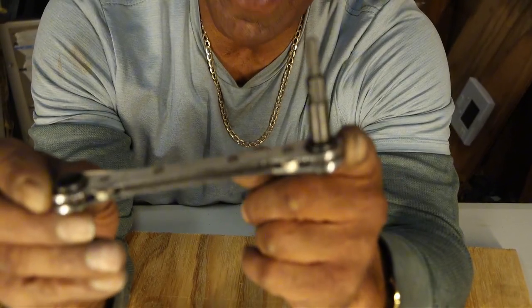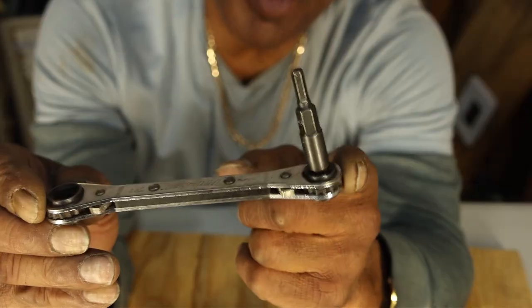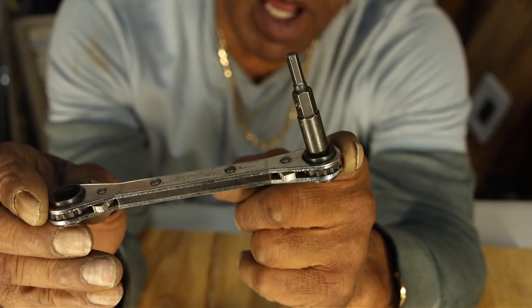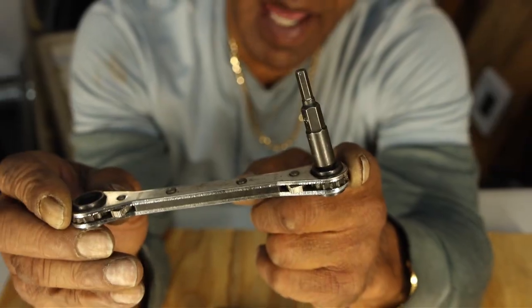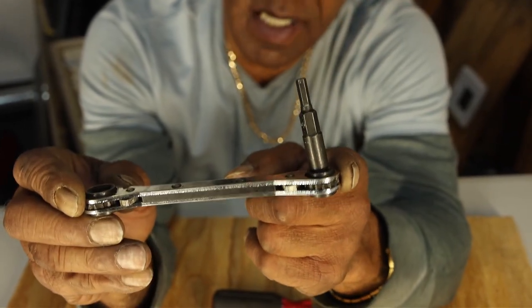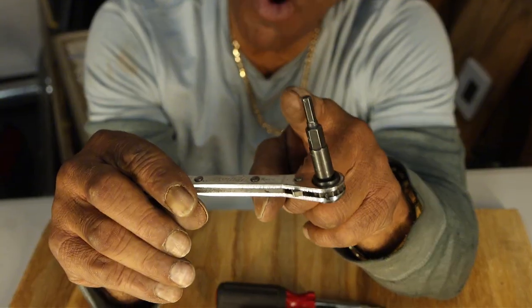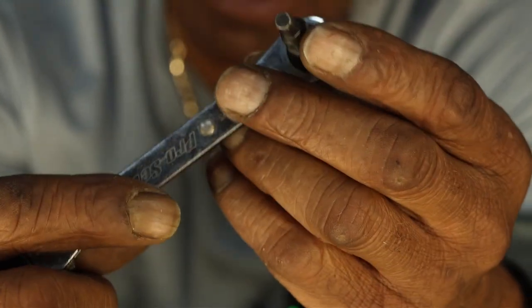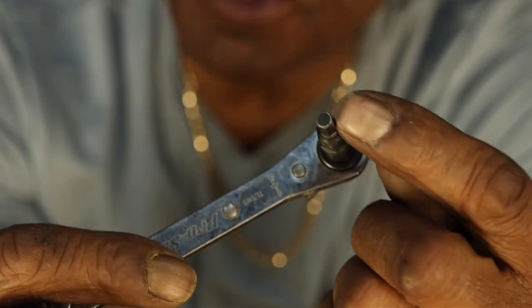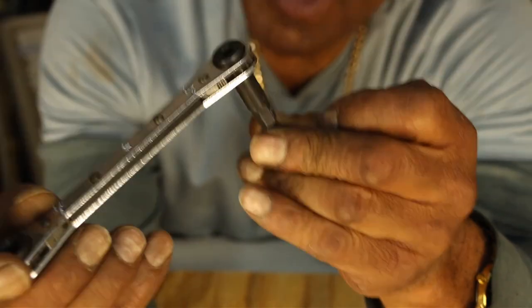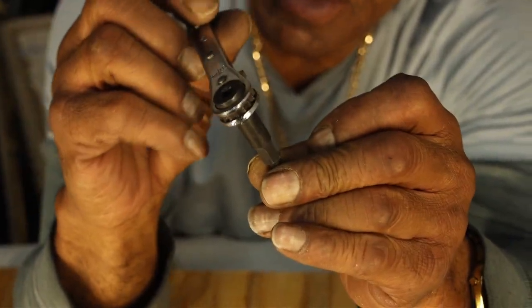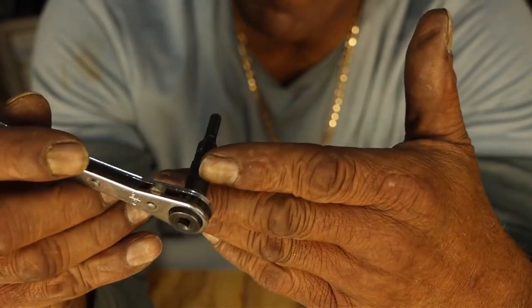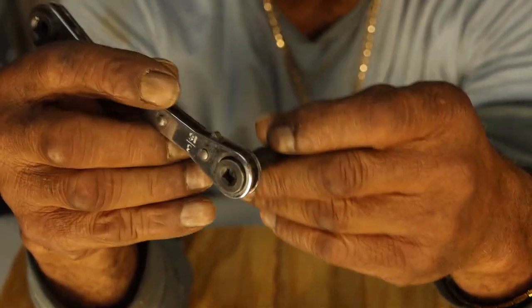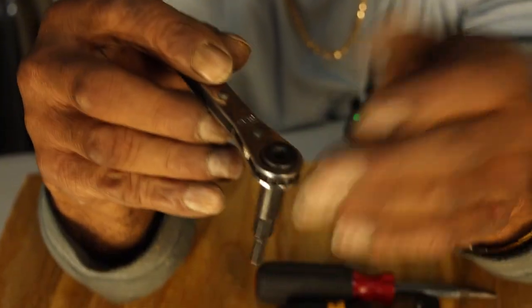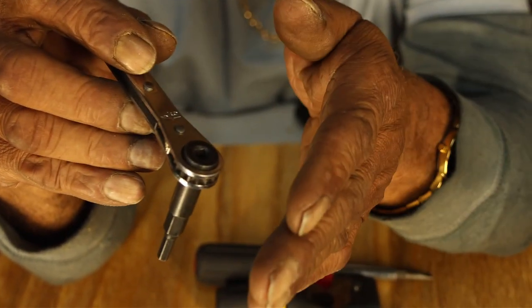On a new air conditioning system, when you purchase it, it will have Freon locked inside of the outdoor condensing unit. This small Allen key, that's basically what it is, an Allen key. The small one will open the liquid side of that system once you have totally connected, vacuumed it down, and you're ready to release the Freon from the outdoor unit into the system.